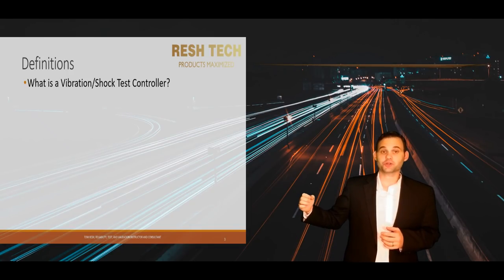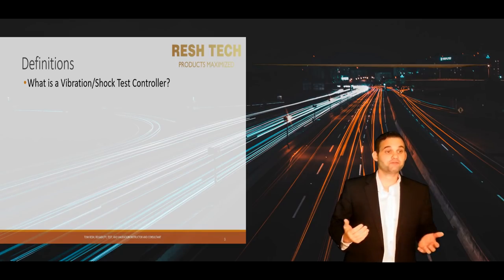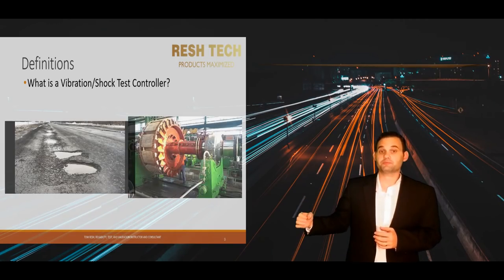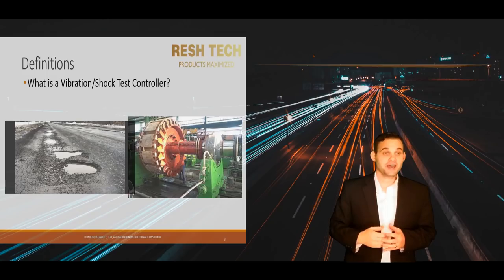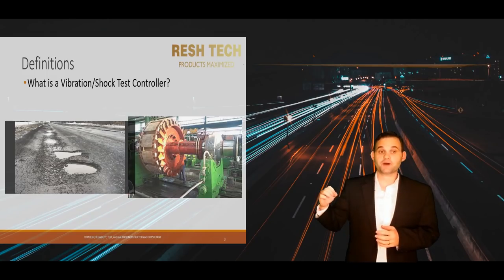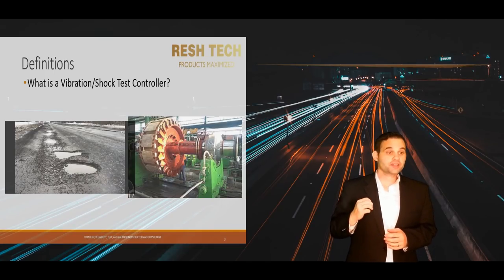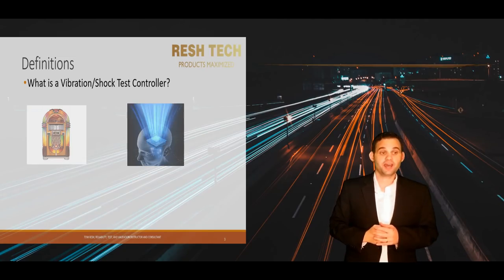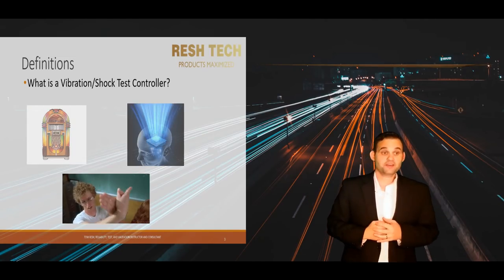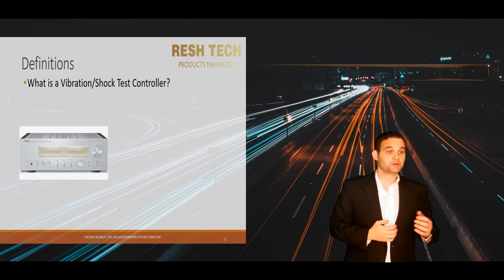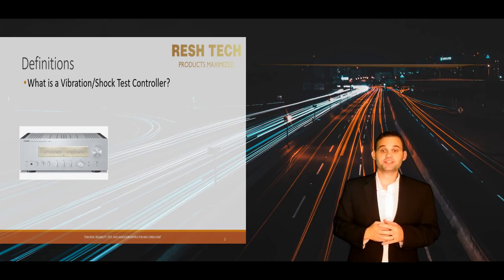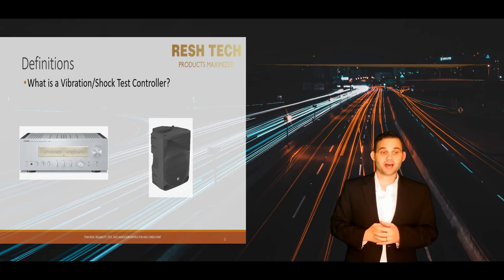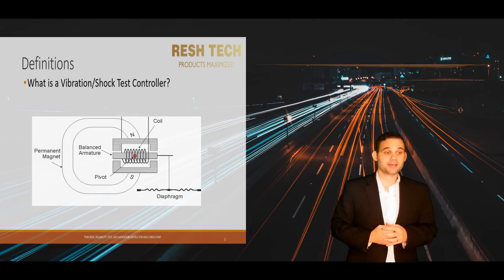A vibration and shock test controller is used to produce simulations of environmental and system-generated vibration and shock excitations. As discussed in part 1 of my two-part series, you can think of the controller as part music player, part your brain, and also your hands. The vibration test amplifier is like a stereo amplifier, and the vibration test system is like a giant loudspeaker, which has similar components such as a field coil and an armature.